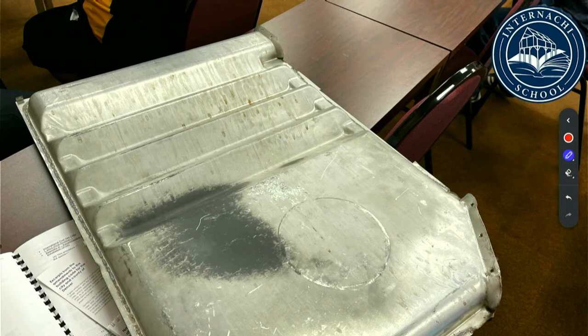This shows where the black is coming across, and you can see where the actual flame impingement was. If you're able to pull a blower fan out and get into learning more about these things, that's how they do it. You get up there with the mirror and peek up in here. Once you start seeing the black stains in there, that's where you're going to be focusing your attention for the cracks.